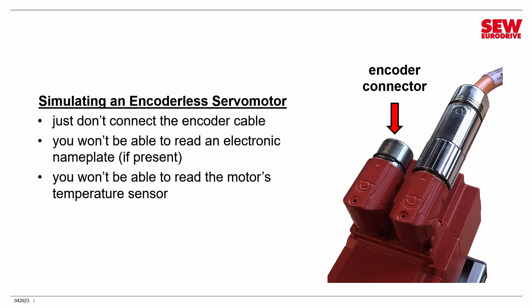But what it does mean is when you configure the motor and commission it, don't tell it it has a temperature sensor because the VFD won't be able to find it, and that will cause a fault.